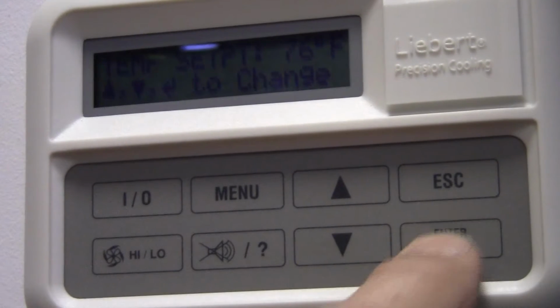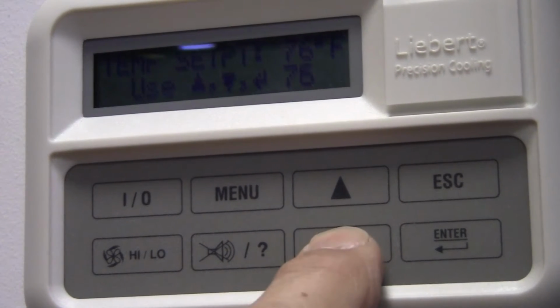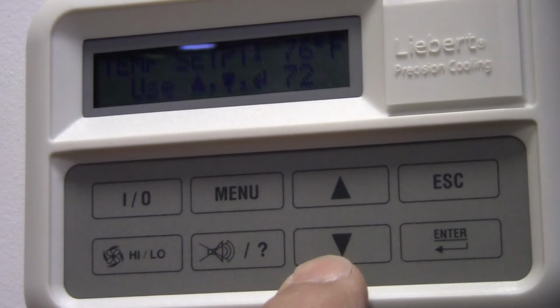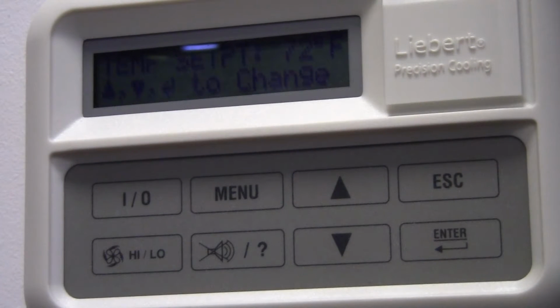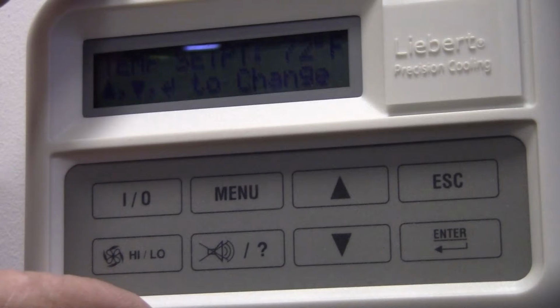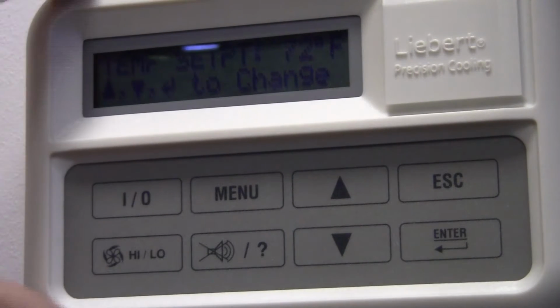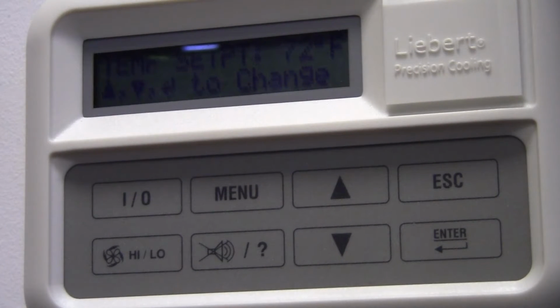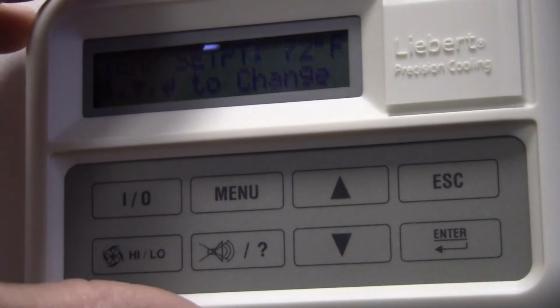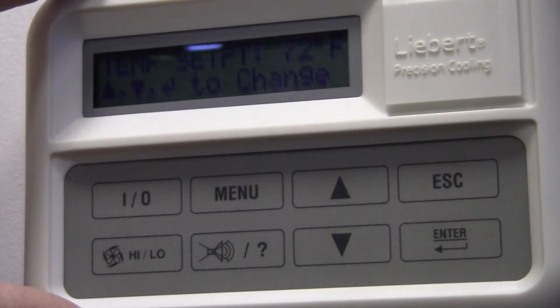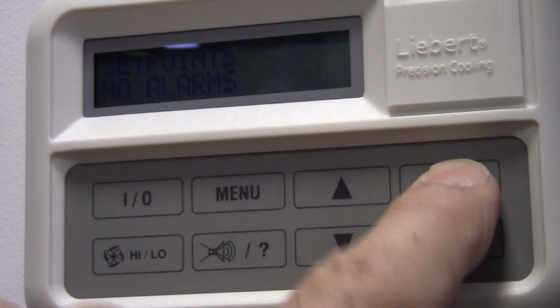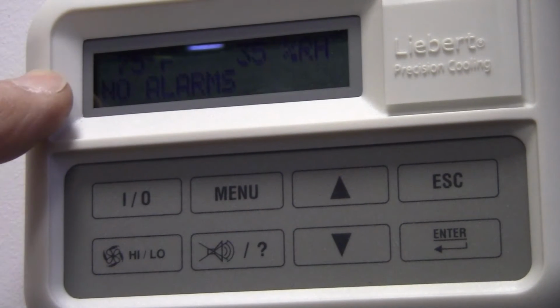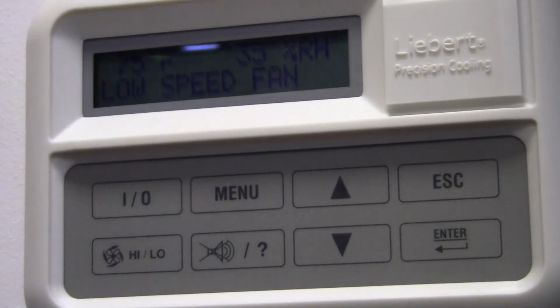We're going to change temperature set point 76, enter to change. I want to change it back to 72, enter. Let's see if the unit does not allow the compressor to first start on, and it appears that it does not. I do not hear that compressor, which is a good thing. There's supposed to be a built-in 2 or 3 minute time delay to allow your refrigerant gases to settle out on the system. I'm going to hit escape and just go back to normal. We're at 75, we have no alarms, we're at 35% relative humidity.